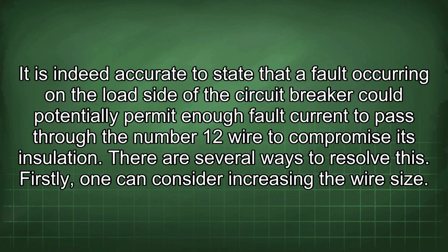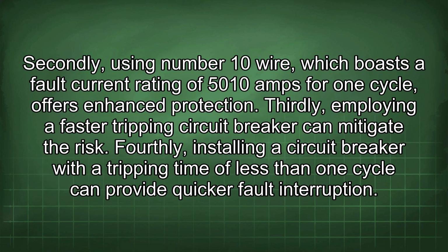There are several ways to resolve this. Firstly, one can consider increasing the wire size. Secondly, using number 10 wire, which boasts a fault current rating of 5010 amps for one cycle, offers enhanced protection. Thirdly, employing a faster tripping circuit breaker can mitigate the risk. Fourthly, installing a circuit breaker with a tripping time of less than one cycle can provide quicker fault interruption.